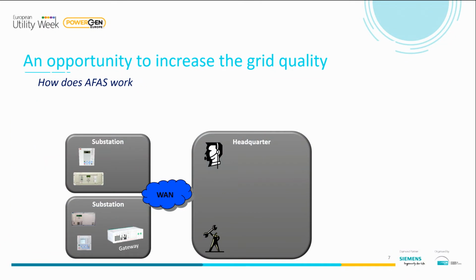Let's see how it works. The way it works is not that hard. From a logical point of view, the substation and the headquarters are linked with one another. In the substation, you've got recorders, DFR, DPR, and the idea is to go from the lightning strike to the desk. Let's say we've got a fault, a lightning strike, for instance.